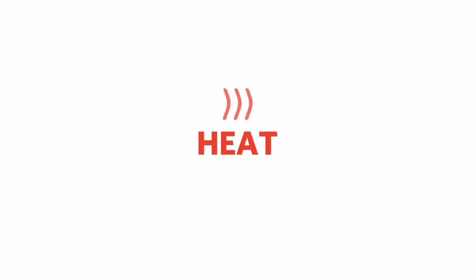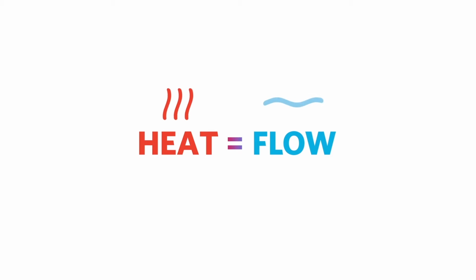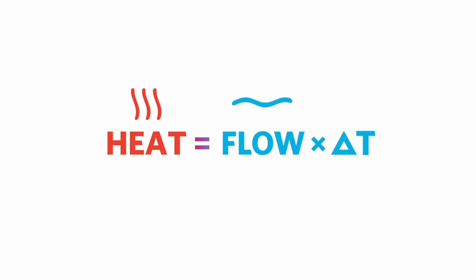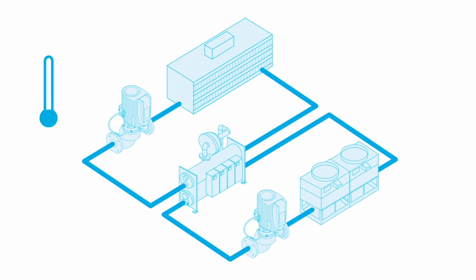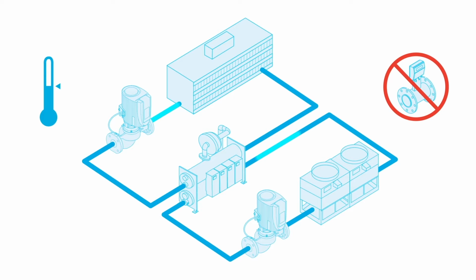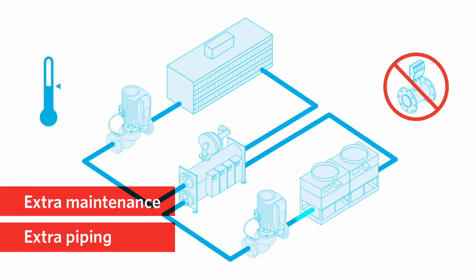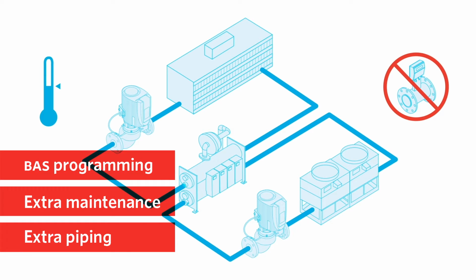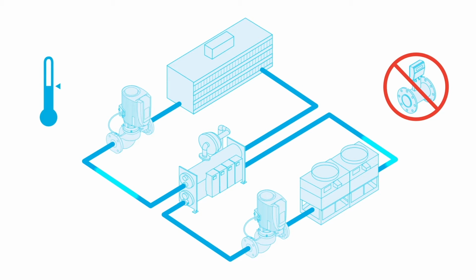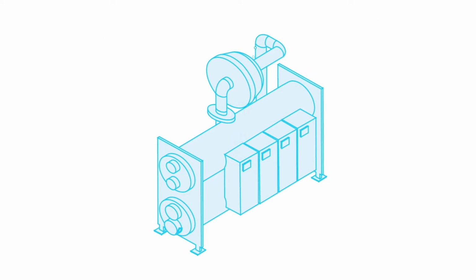In any chilled water system, knowing the cooling load is the starting point. Cooling load in a building can be calculated by multiplying the system flow rate by the change in temperature, usually expressed as delta T. Traditionally, HVAC systems in buildings were designed only to meet temperature set points. Among other differences, this avoided the expense of a flow meter, which is important because the addition of a flow meter also adds extra piping, extra maintenance, and additional points to program and commission into a building automation system. But this design approach reveals a weakness.